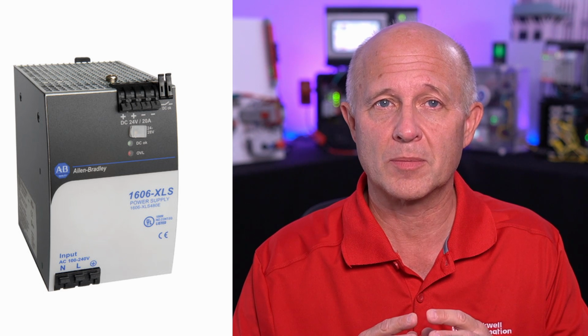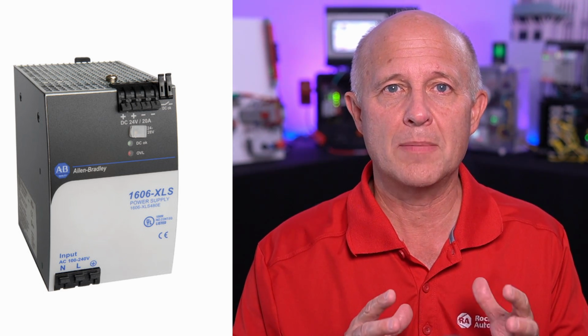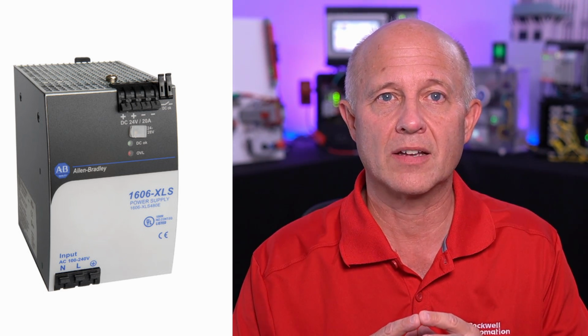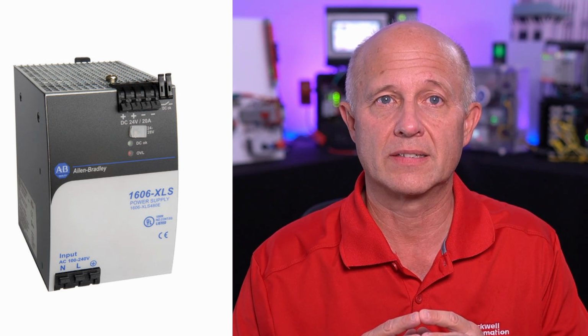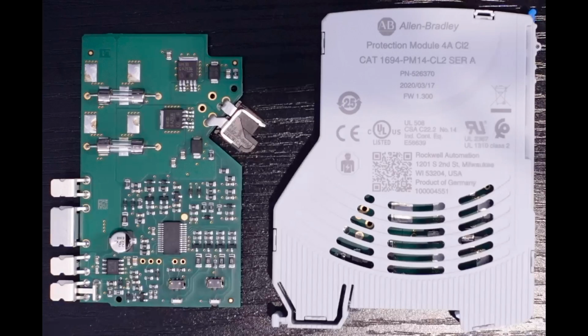On the other hand, 24 volt DC power is supplied from a switch mode power converter. It's only capable of providing a limited amount of current based on the power rating of that device. These new electronic circuit protectors operate with a combination of a solid-state switching component and an integrated circuit chip. They're specifically designed to quickly detect short circuits and small overload conditions that are typically found in a 24 volt DC circuit. So, let's take a look at the Allen-Bradley Bulletin 1694 line of electronic circuit protectors.